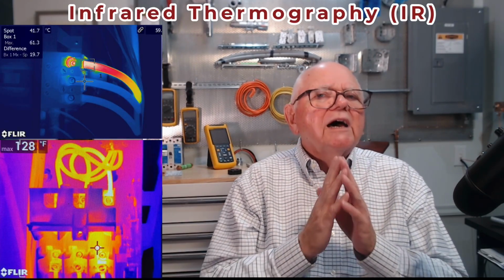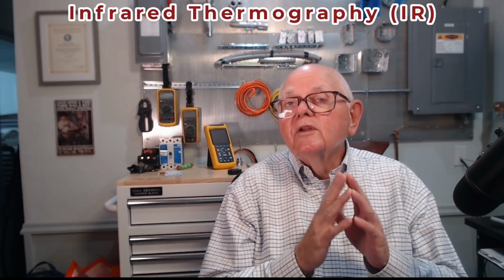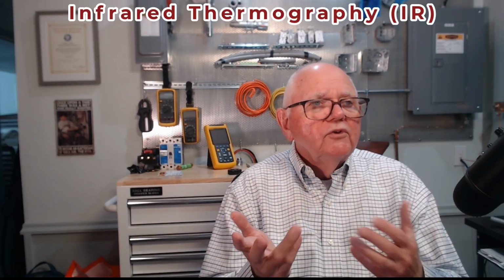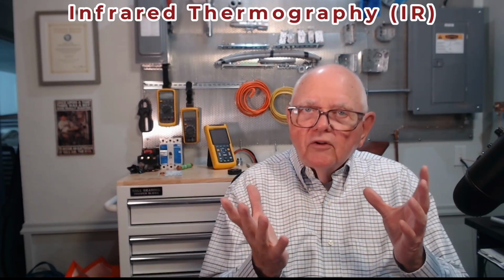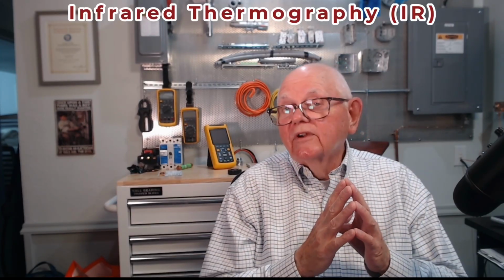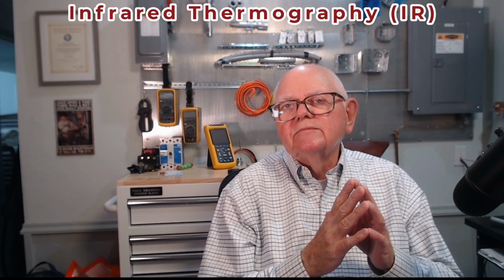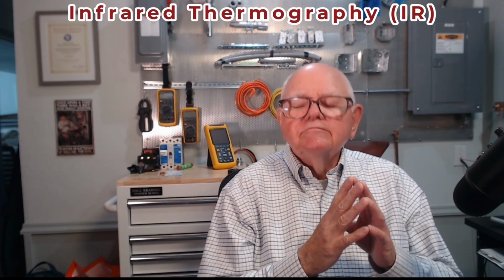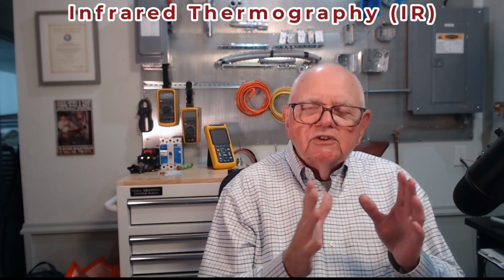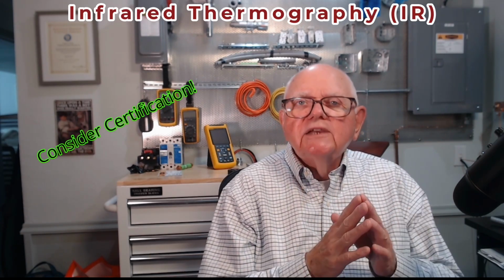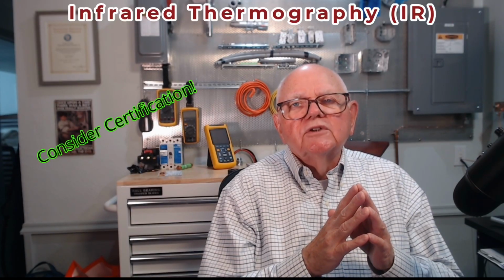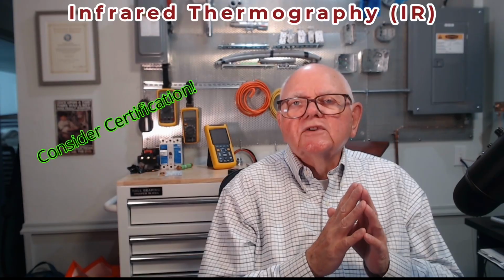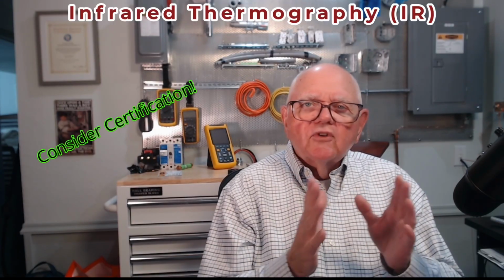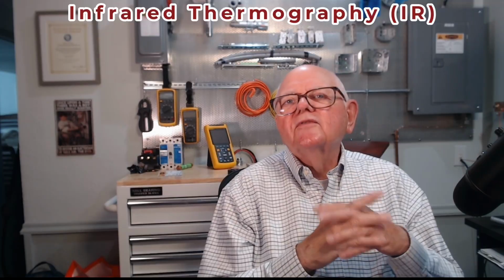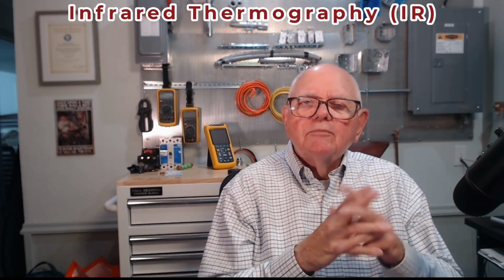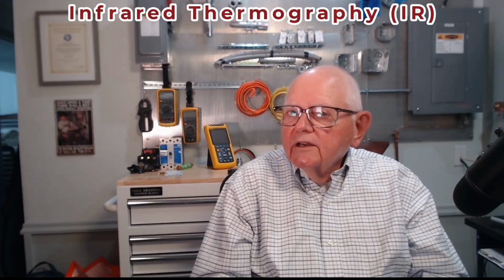But remember, there's a lot of things that go into infrared thermography. You can buy infrared cameras that go on your smartphone. You can buy an infrared camera that's part of a multimeter. Or you can go out and buy some very sophisticated IR equipment, can't you? Now, depending on what you're doing in your facility, buy the equipment that meets your needs. Above all, make sure that you're properly trained on it. You can get certifications regarding electrical testing of your equipment and interpreting your electrical images. Record all the data, keep track of it. Typically, we do infrared thermography every year, but depending on what your application is, of course, follow your electrical maintenance program as to what you need.